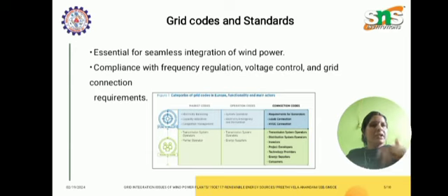When LOM occurs, neither the voltage nor the frequency is controlled by the utility supply. Normally, islanding is the consequence of a fault in the network. If an embedded generator continues its operation after the utility supply was disconnected, faults may not clear since the arc is still charged.